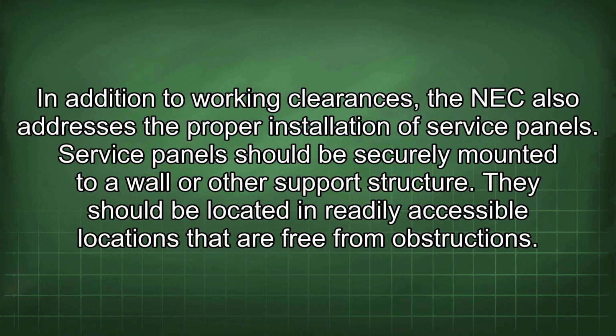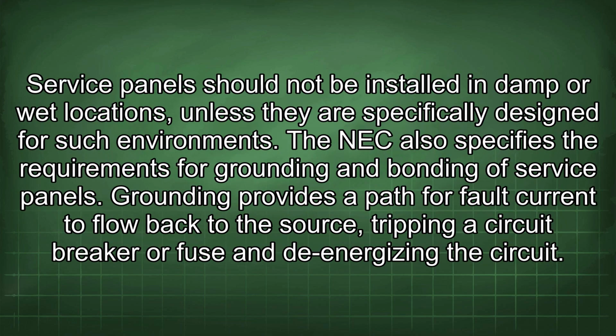In addition to working clearances, the NEC also addresses the proper installation of service panels. Service panels should be securely mounted to a wall or other support structure. They should be located in readily accessible locations that are free from obstructions. Service panels should not be installed in damp or wet locations unless they are specifically designed for such environments.